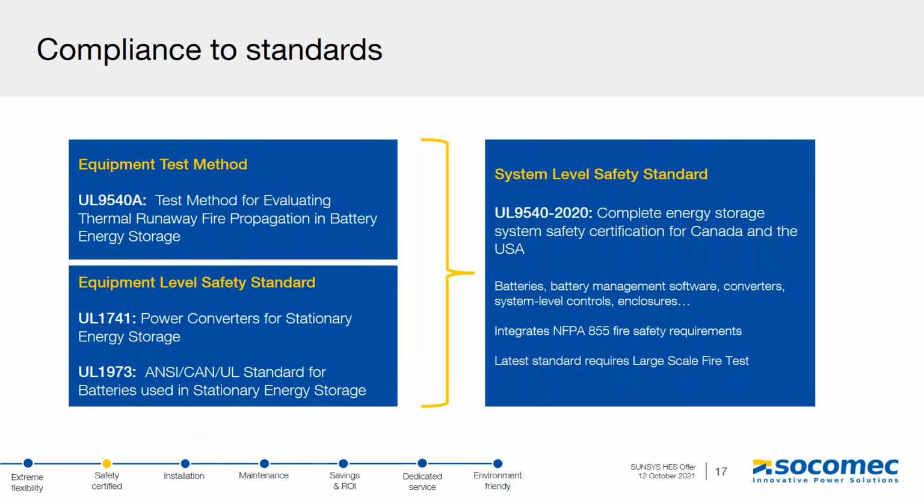Standards, I just wanted to touch on this real quickly. Large scale fire tests we've talked about. There are component level standards for both batteries and converters. These are met at the very latest versions of both of these. Then all of these together combine to make a system level safety standard, which is somewhat confusing because it sounds a lot like the battery test method, but it's UL9540 without the A, the certification for the energy storage systems.